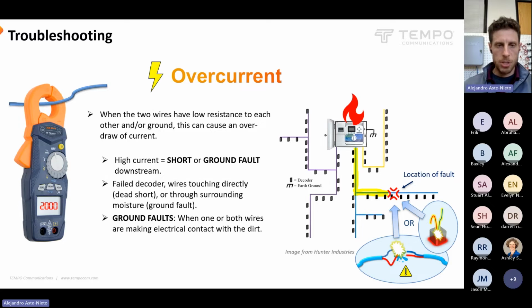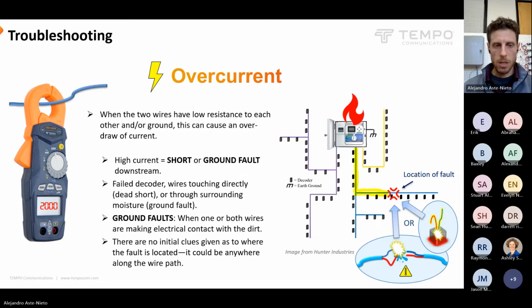So I mentioned ground fault. That can be where both wires have some kind of contact with the dirt, or it can just be where there's one wire with contact to the dirt and there's current leaking only through that one wire. And in this situation, the controller is not going to give you a whole lot of information about where this problem's happening. It's not going to say there's a short here and it's only affecting these decoders down here.